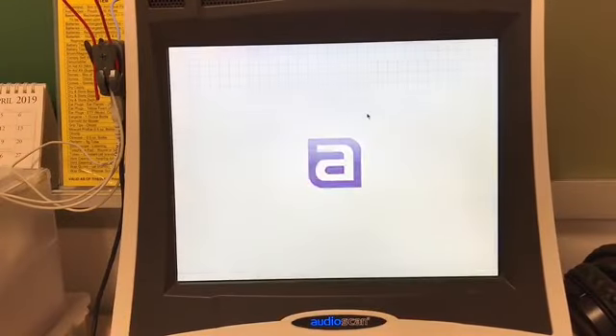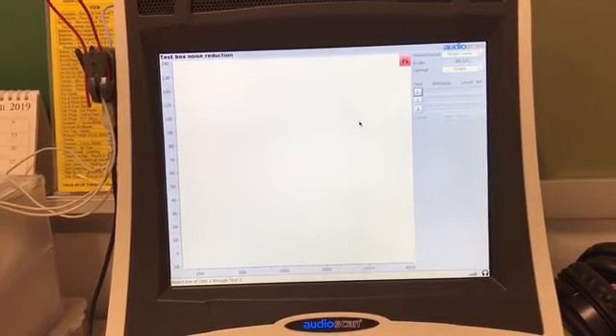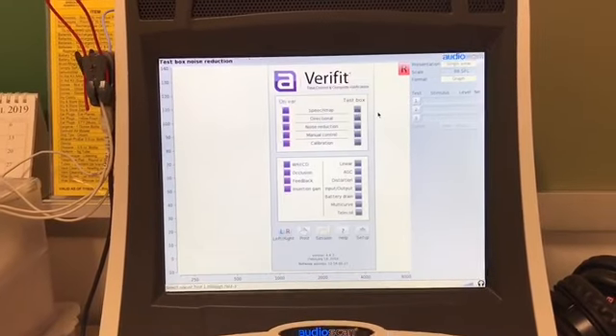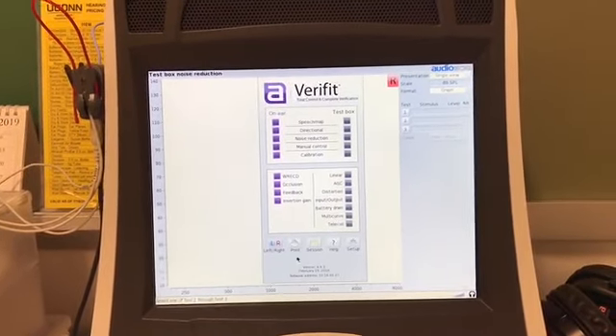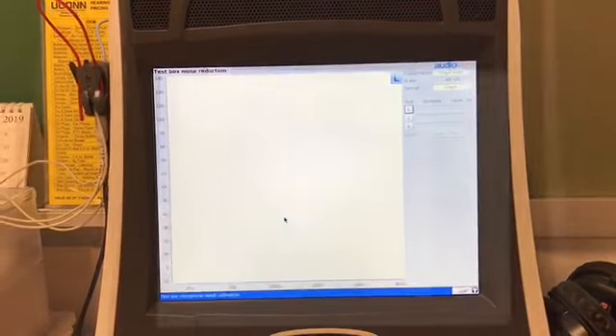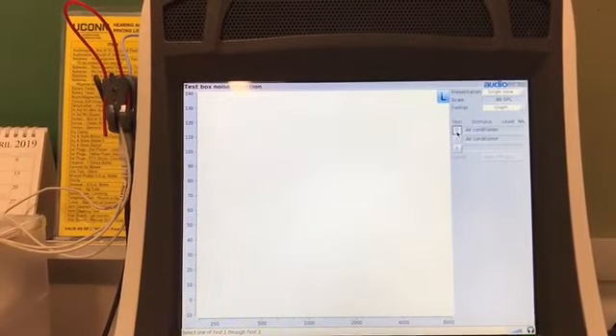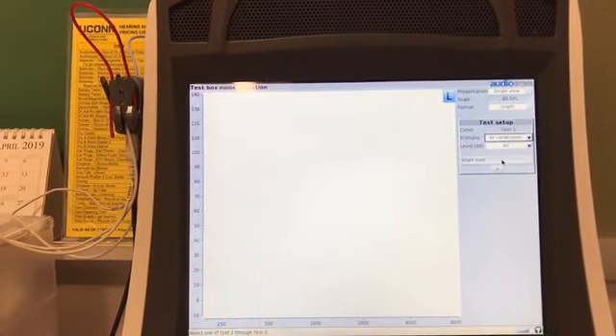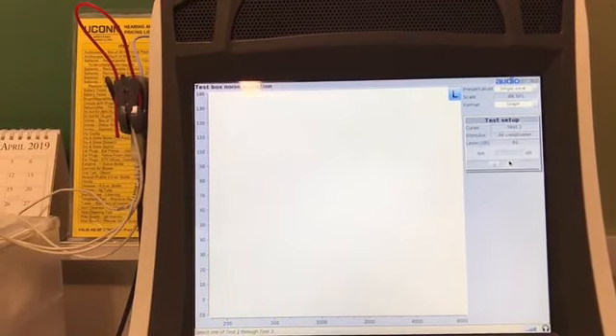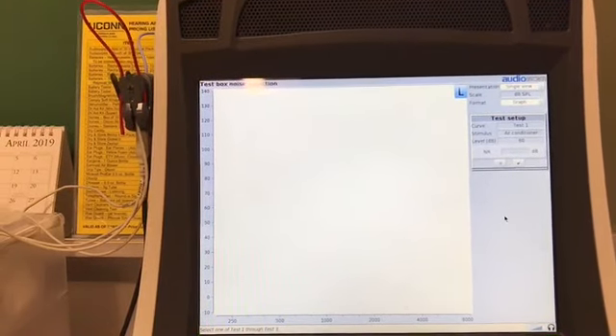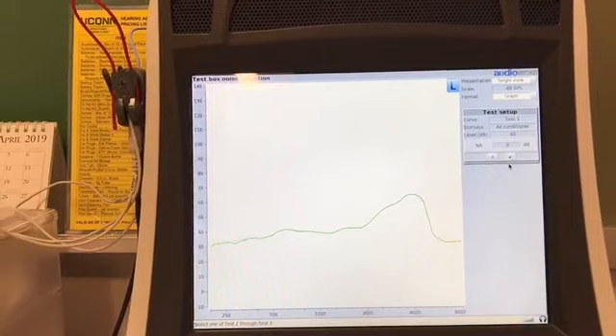Now that the hearing aid is all set up and all the noise reduction settings are off, we move to the VeriFit. The VeriFit wants to go to the right side of the coupler, but Stephanie quickly switches to the left. Now she's going to run the test to create that reference line with the noise reduction settings turned off.